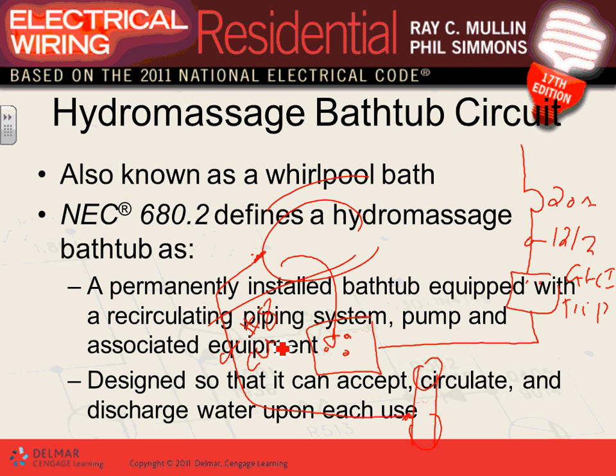And the bonding conductor between the frame of the hydromassage pump and the water is to make sure the water pipe and the frame are at the same potential. So when you're sitting in your hydromassage bathtub, the water is bonded through the pipe, everything is sitting at the same potential, so you don't get electrocuted. Any questions? That's it. 20 amp circuit, number 12, dedicated. Make sure it's GFCI, trip to a receptacle, plug it in.